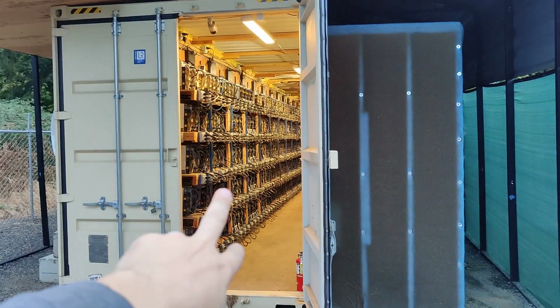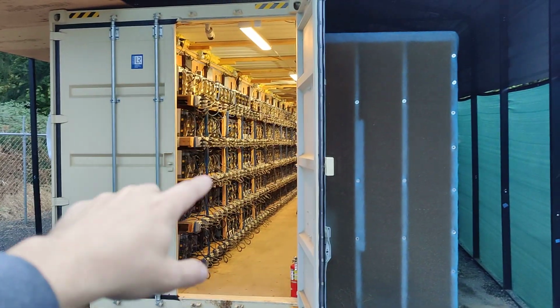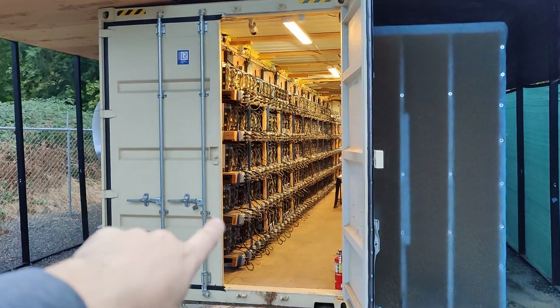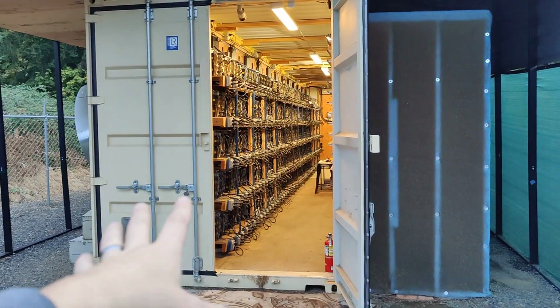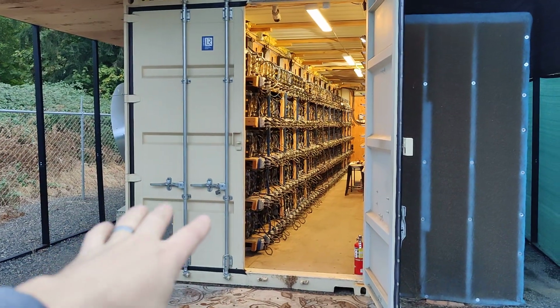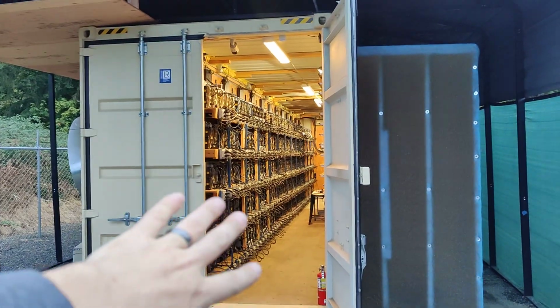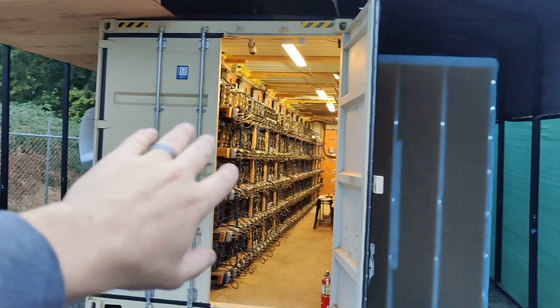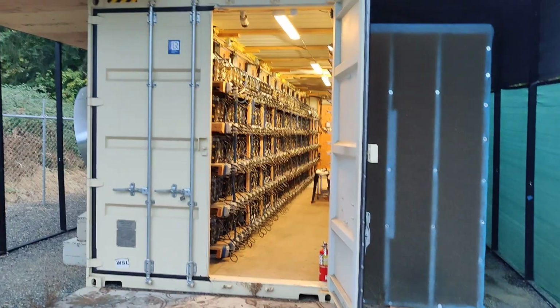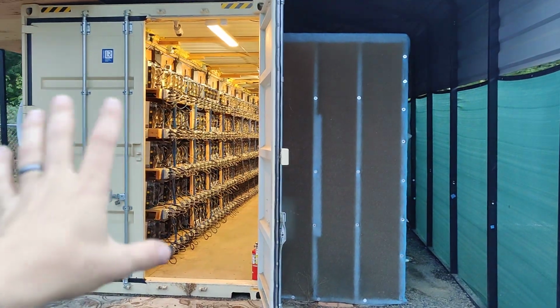I put the humidity sensors there. I know it's not going to be more than 70 throughout the rest of this winter, fall, and spring probably. So all I have to do is make sure that at 70 they do not overheat, and then run them as slow as possible to handle that 70 degrees. That's how they're set up right now.